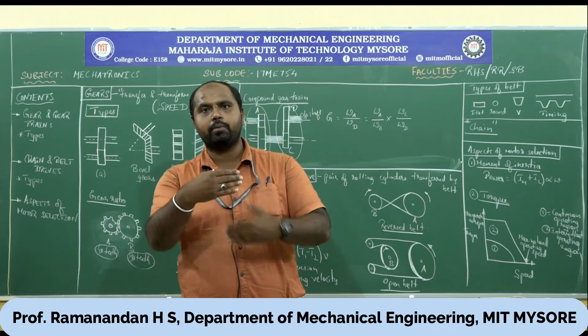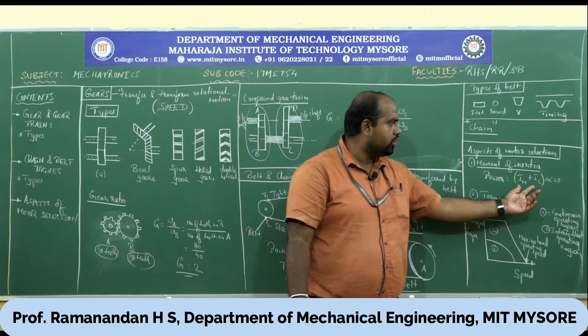Because of rotation, moment comes into the picture. So the moment of inertia Im of the motor and the moment of inertia of the load IL, the summation of these two multiplied by alpha into omega. Alpha is angular acceleration, and omega is obviously angular velocity. All these clubbed together will give what should be the power of the motor, how to select the power of the motor, or how it should be calculated, so that moment of inertia can be easily balanced or overcome.